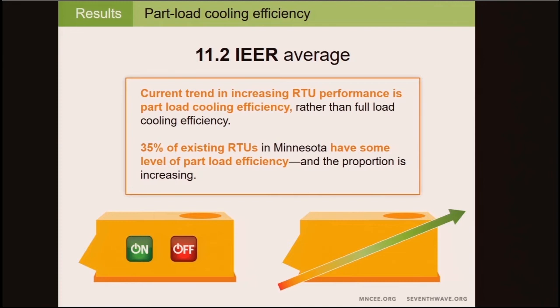The current trend in increasing RTU performance is with respect to part load cooling efficiency rather than full load cooling efficiency. For instance, variable speed compressors, often inverter driven, allow for part load efficiencies over 18 IEER. We calculate that 35% of existing RTUs in Minnesota have some level of part load efficiency, and that proportion is increasing. For existing RTUs in Minnesota with part load cooling efficiencies, the average IEER is 11.2.